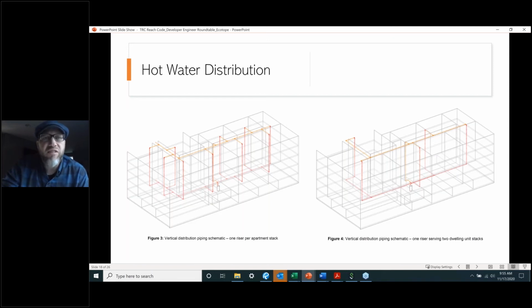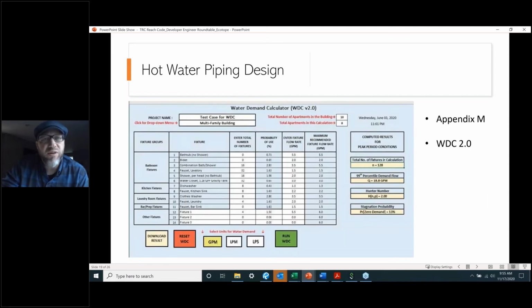There's another strategy to reducing the UA, and that's to right size. Hot water piping design has been under the microscope for a while. We've had theories, technologies, and sizing tools based on really old data. So both with sizing of the central plants, which is what the EcoSizer does, and then IAPMO has released the water demand calculator. This is a great tool to help design right-sized plumbing.